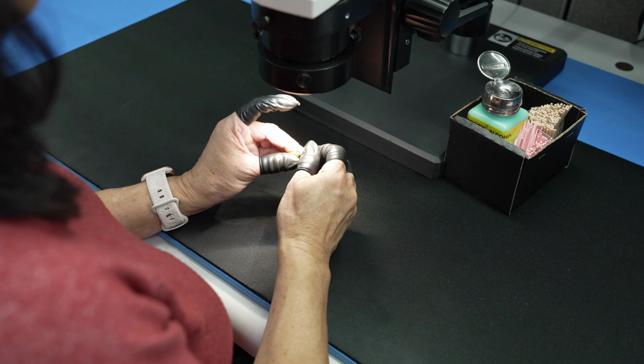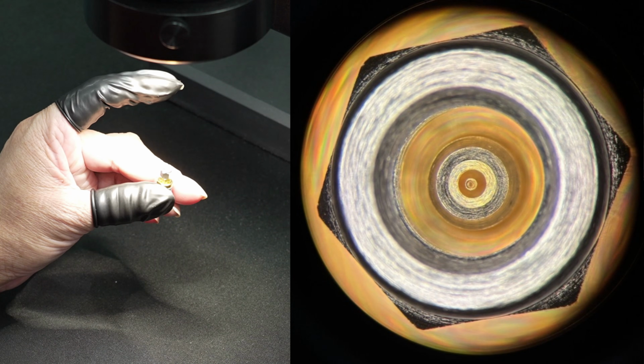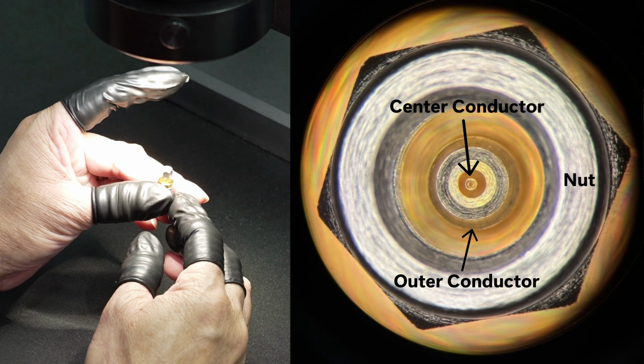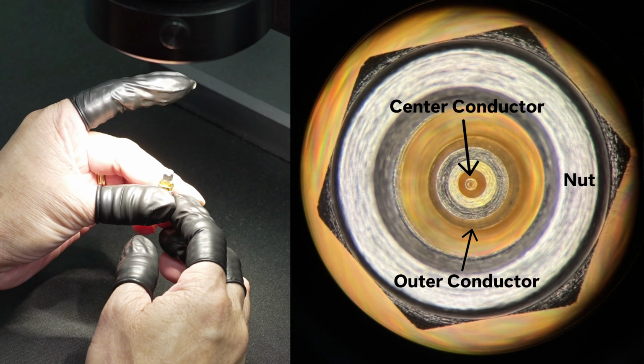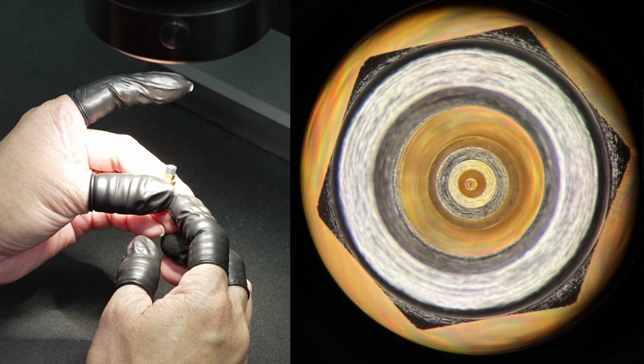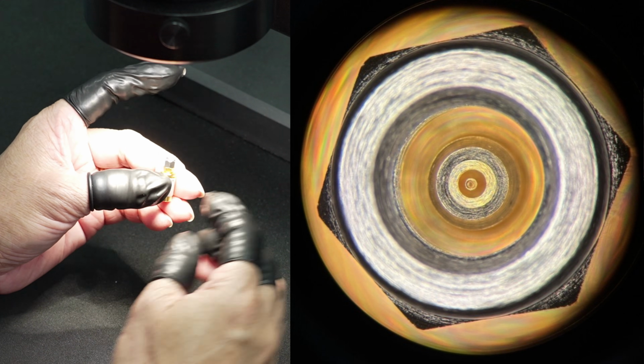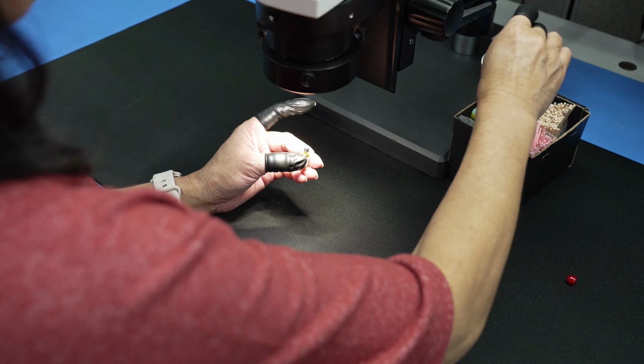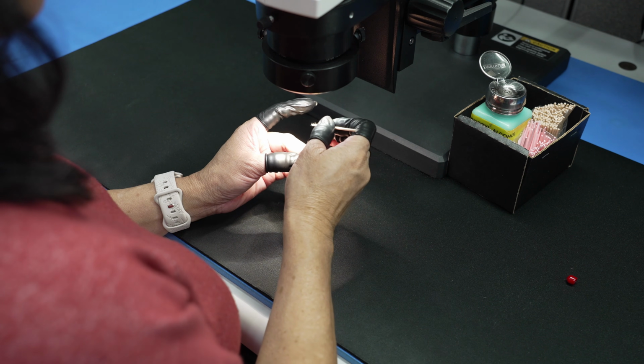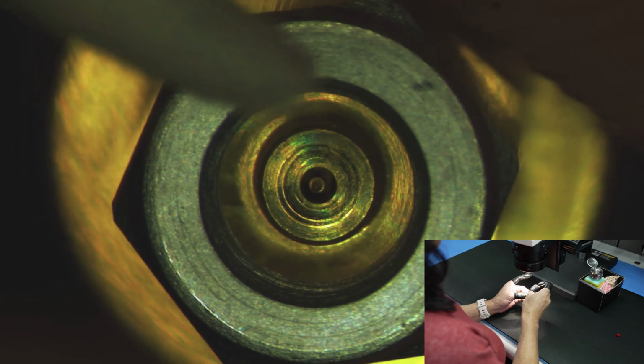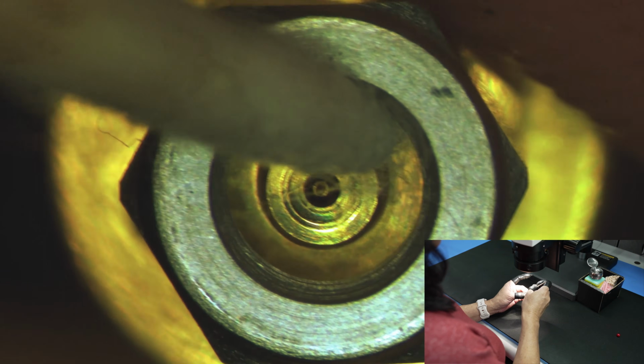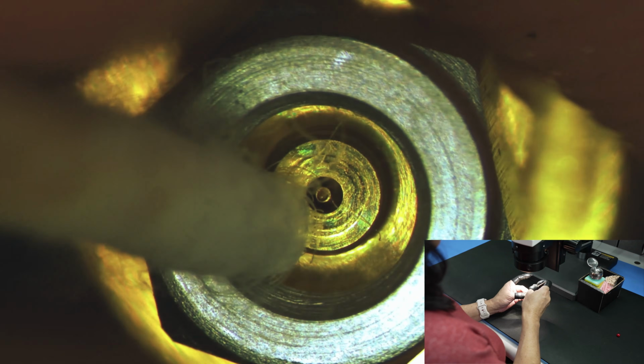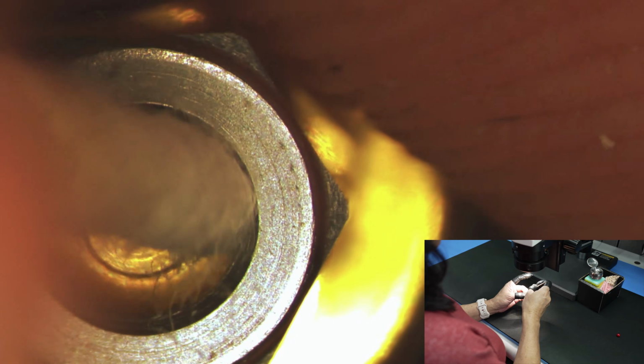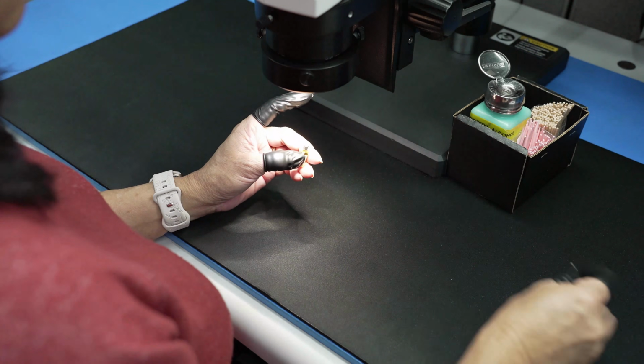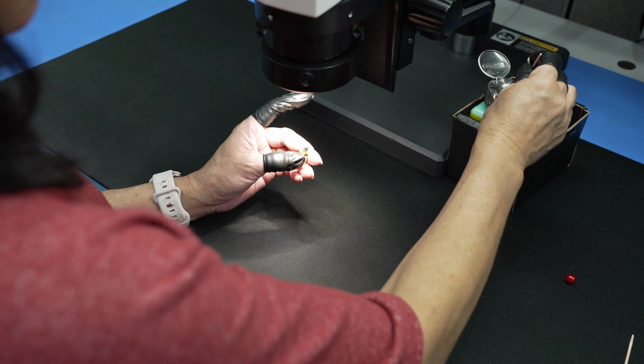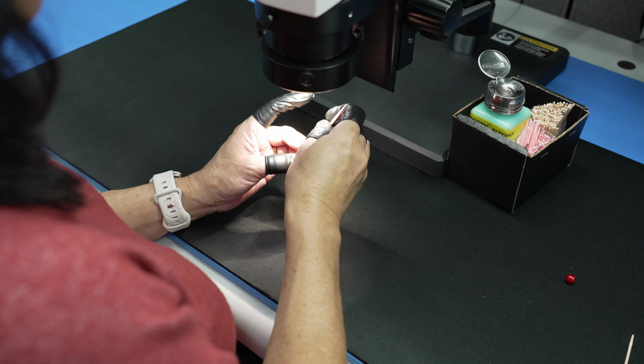Moving on to male devices, which have a nut. Inspect it under the scope for concentricity of the center conductor inside of the outer conductor. Look also for any debris, residue, scratches, or damage on the mating surface, pin, and threads. To clean the device, use a cotton swab dipped in isopropyl alcohol to clean the mating surfaces. Take care to avoid the center conductor pin especially. A foam swab dipped in alcohol can be used to clean the threads and outer conductor.